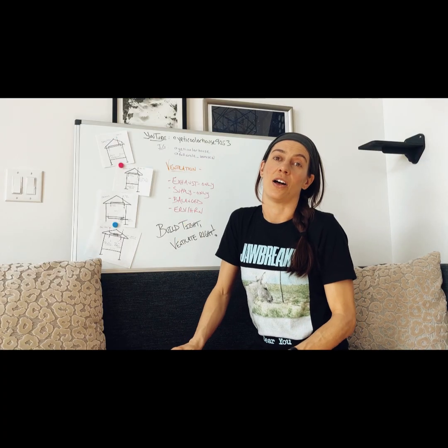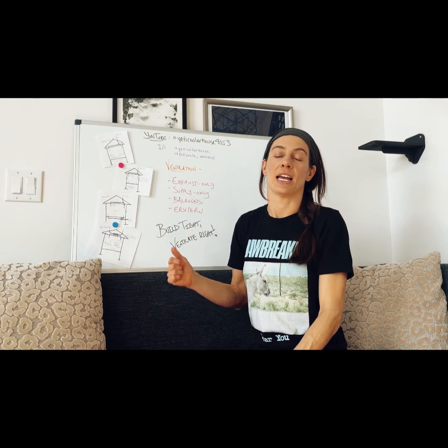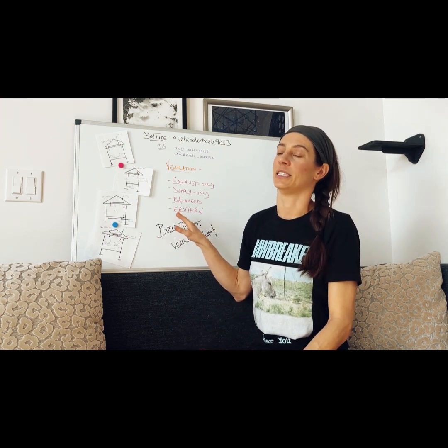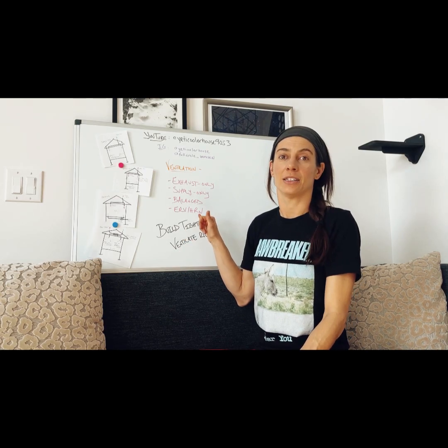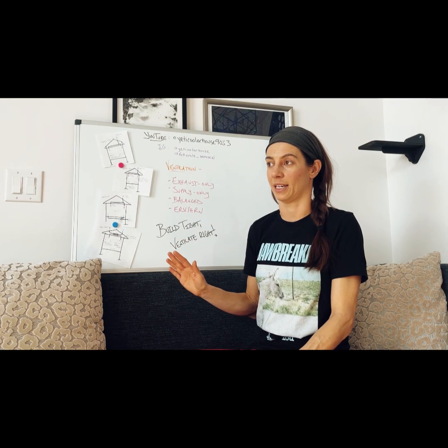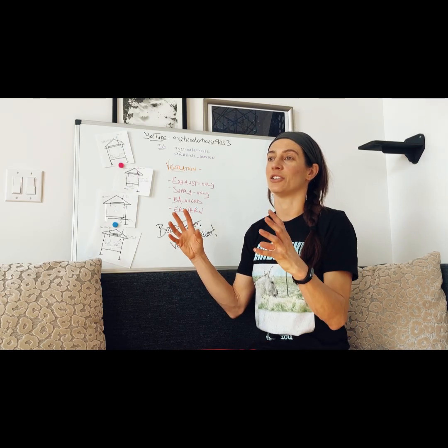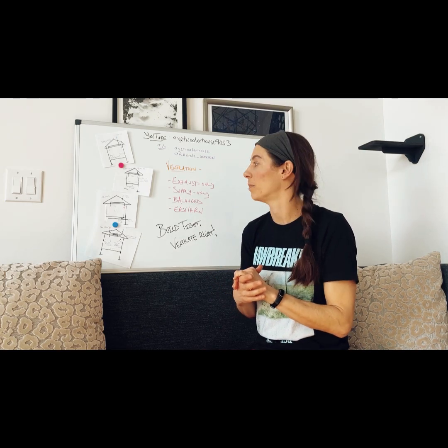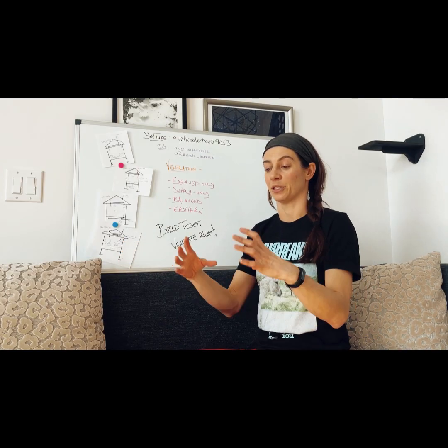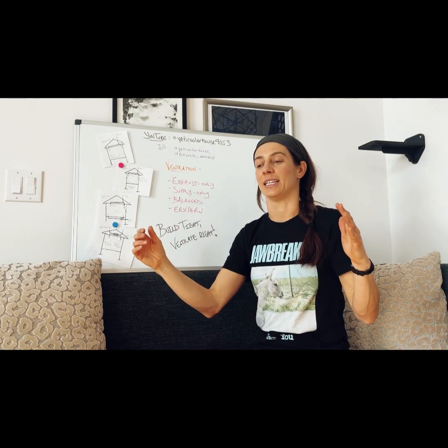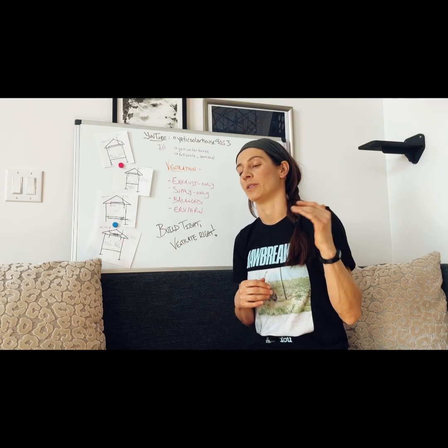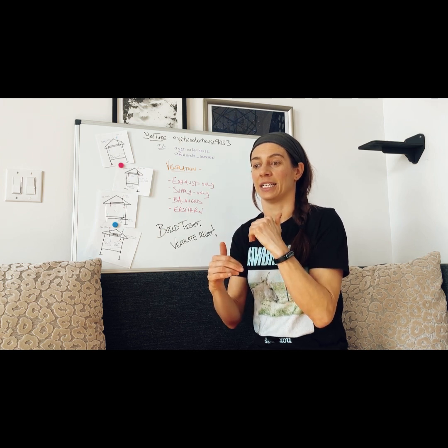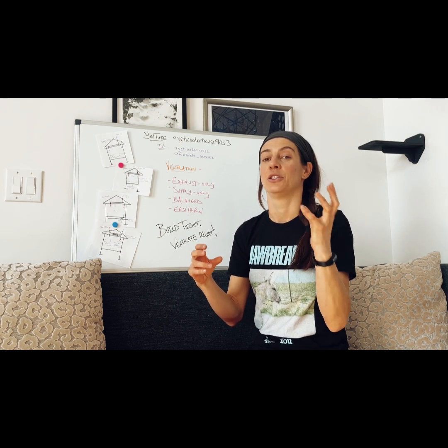You could also just install an ERV or HRV. This is an energy recovery ventilator or heat recovery ventilator. The energy recovery ventilator deals with humidity. The heat recovery ventilator is just heat. So both are ventilating, but the ERV is transferring heat and moisture, and the HRV is just the heat. So think about, and I'll zoom in on this here, there's a core, and basically the ERV is exhausting while supplying at the same time.